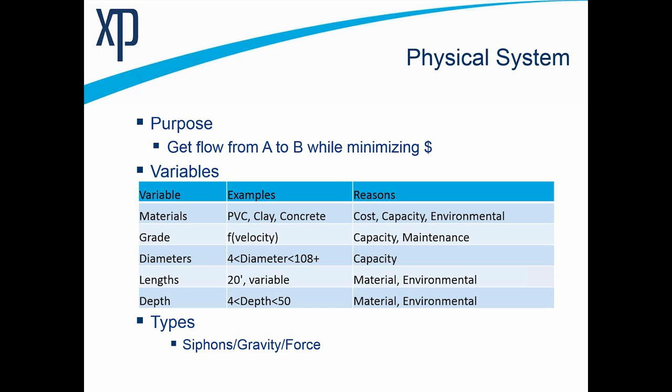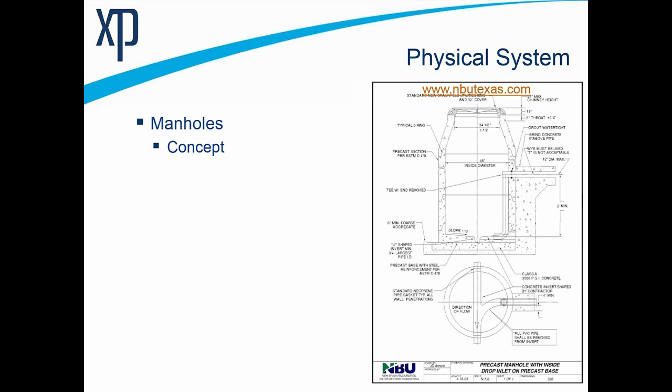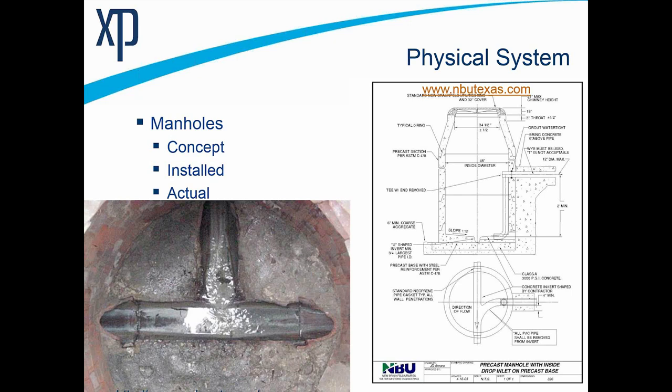Those pipes need connections. The type we're most familiar with is the manhole. If you see a drawing of a manhole, there are quite a few different parts. Generally if you're just a hydraulic modeler, you may think of a manhole as a dot with a nominal volume in it, but there are really lots of different pieces to the whole life of a manhole. After installation it looks beautiful — hand-laid base. But after some amount of time in that environment, different things happen. In this example, flow comes from top down and left to right in a brick manhole. From inspection you can see it's maybe a third to half full, but from the bench you can tell it certainly surcharges under different conditions.